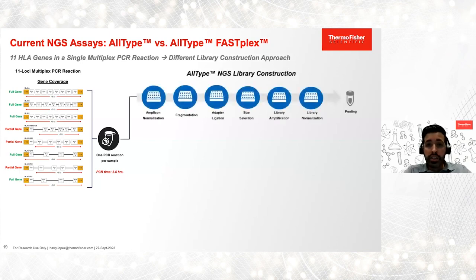The main difference between AllType and AllType FASTplex is the library construction approach. AllType has a traditional library preparation with two normalization steps — one for amplicons and one for libraries. Every single sample goes through multiple steps including fragmentation, adapter ligation, size selection, and library amplification. At the end of the workflow, samples are pooled into a single tube and then proceed to sequencing. The total assay time is eight and a half hours with three and a half hours of hands-on time.